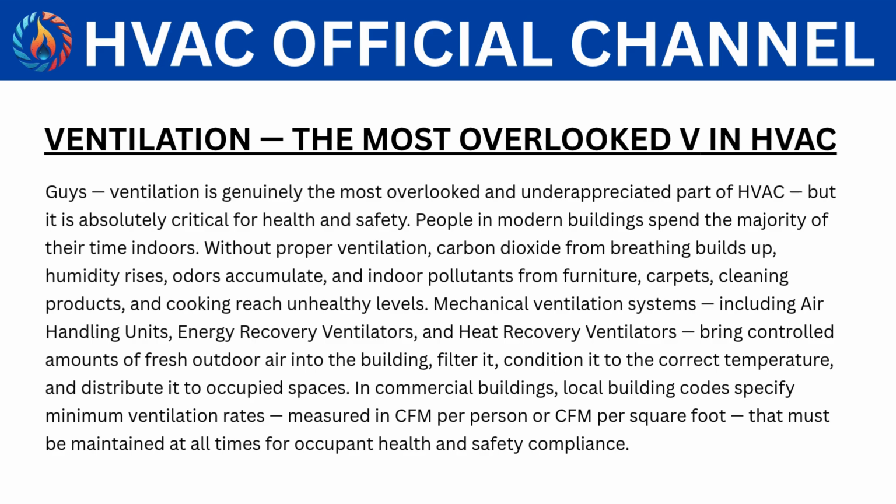In commercial buildings, local building codes specify minimum ventilation rates, measured in CFM per person or CFM per square foot, that must be maintained at all times for occupant health and safety compliance.